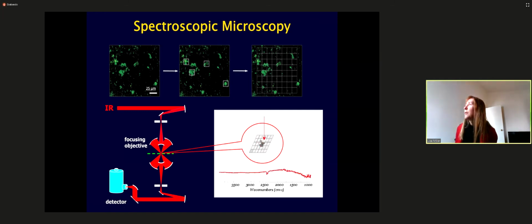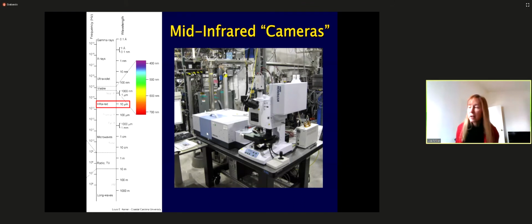All right. So since you don't have the opportunity to actually visit the synchrotron, I'll show you a picture of what an infrared microscope looks like. This is one of our 3 infrared microscopes that we have at Brookhaven. This is the newest of them. This is a Bruker Hyperion 3000 with a Vertex 80v spectrometer. So this spectrometer is where you would do spectroscopy. If you want to do small stuff, you put the beam into the microscope. The beam itself from the synchrotron comes down this pipe down here and into the spectrometer, and then into the infrared microscope from there.